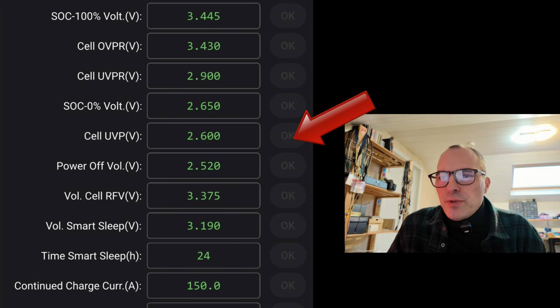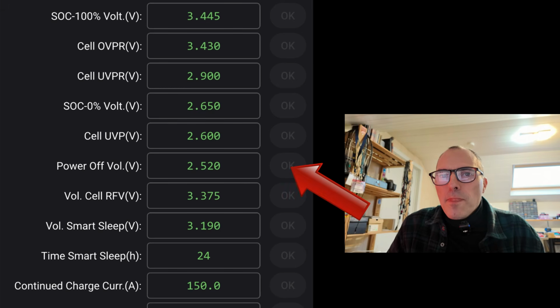Cell under voltage protection. When this voltage is reached for one cell, BMS will disconnect the battery and only reconnect when the under voltage protection recovery is reached, which I set previously at 2.9 volt. Power off. It's the voltage where the BMS will shut down. I have set mine to 2.52 volt. It's recommended 2.5 or above.